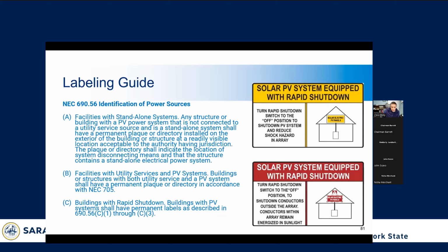So this is just more on the labeling requirements. These labels are for rapid shutdown. Red would be used for a string inverter system. Yellow is used for DC optimizers or microinverters.